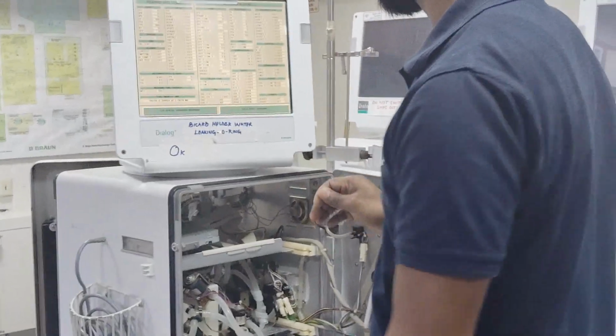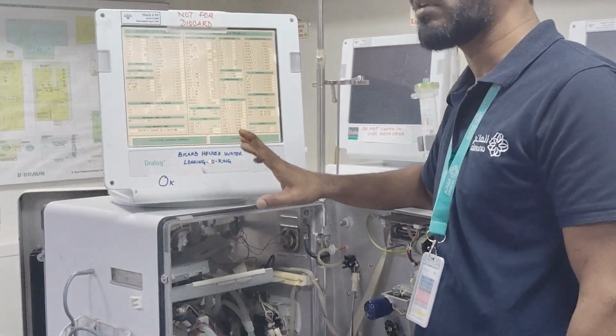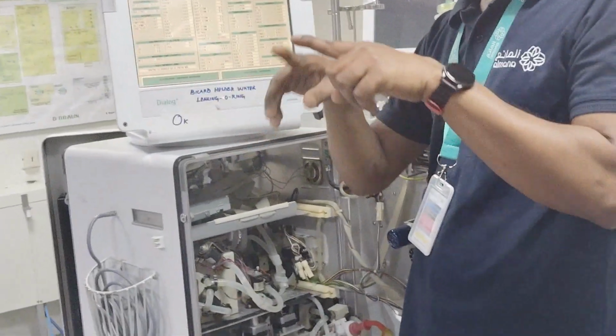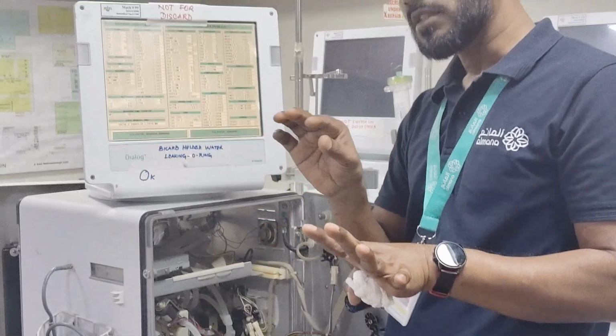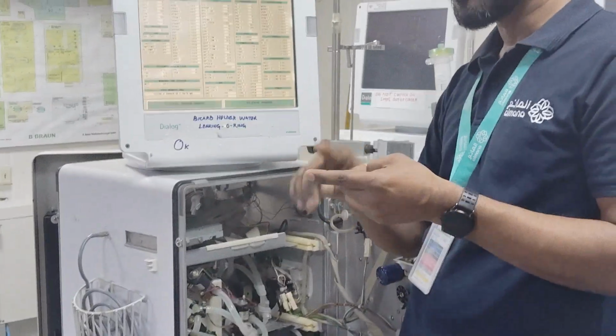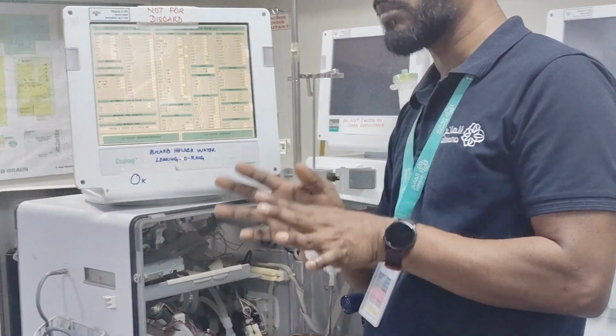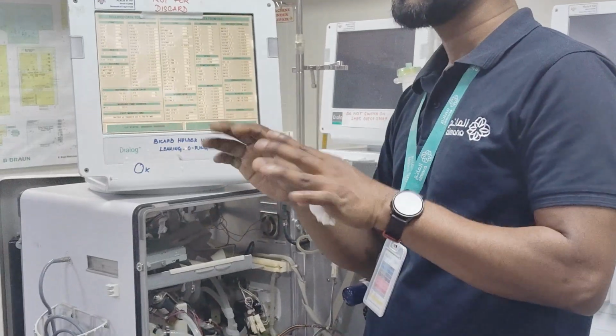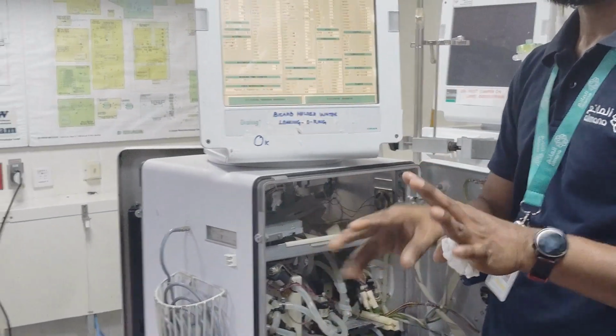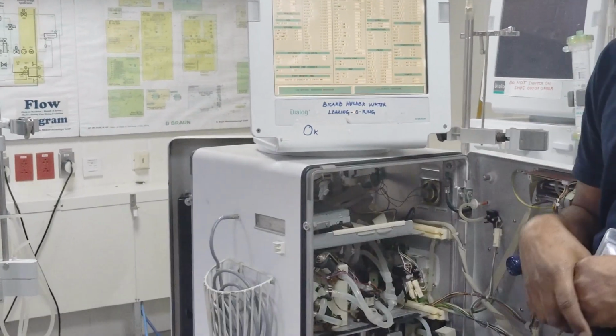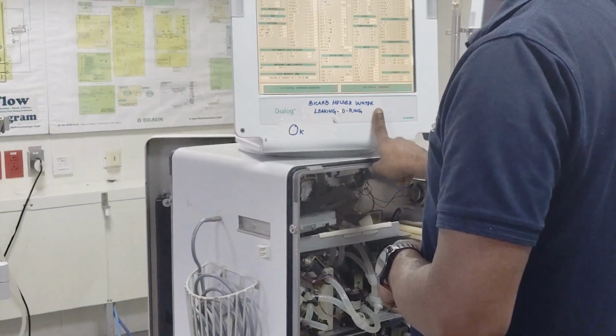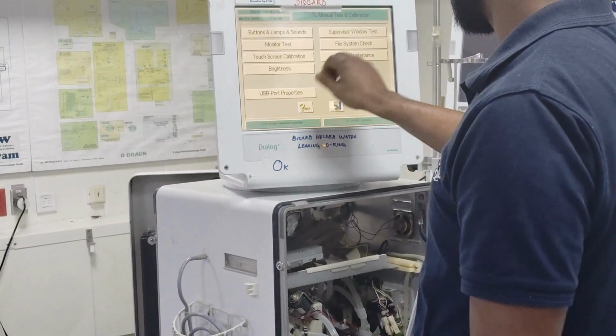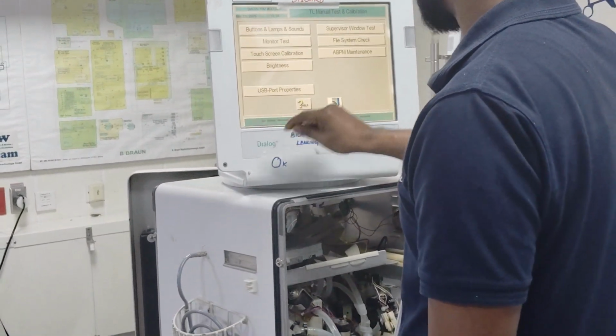So for that calibration, two things can be at fault. One is the display: the touch screen glass has a fault, something wrong in that. If not, the touch controller board inside can be wrong. If not, you are not getting power, or there are software issues. This problem can happen. Now you see that touch screen calibration. I showed you because of these small things.